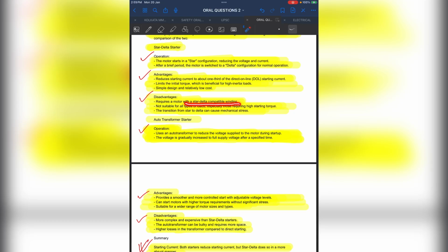Require a motor with a star delta compatible winding. So if the motor has a compatible winding with the star delta configuration, then you can put the star delta starter. It is not suitable for all types of load, especially those requiring high starting torque. Suppose you want to run a motor with a very high starting torque, then you are not able to use this star delta, because it will not provide you a high starting torque. So for high starting torque you have to go for another configuration.